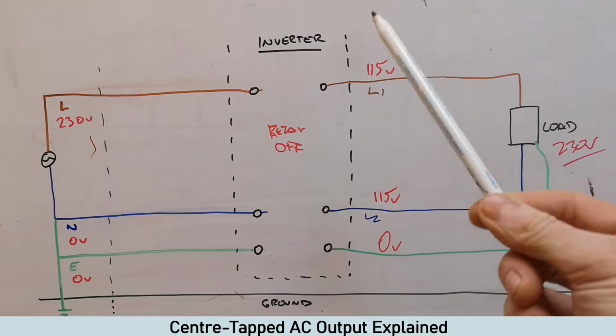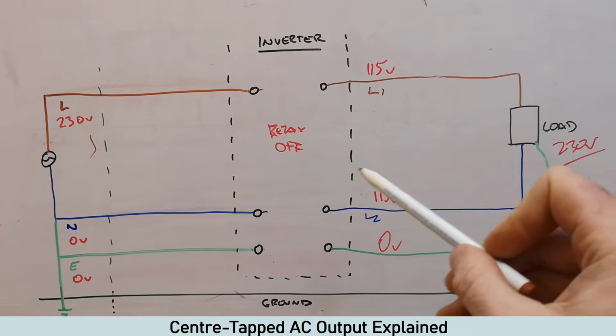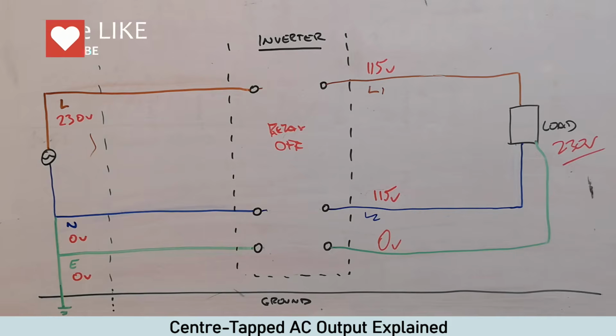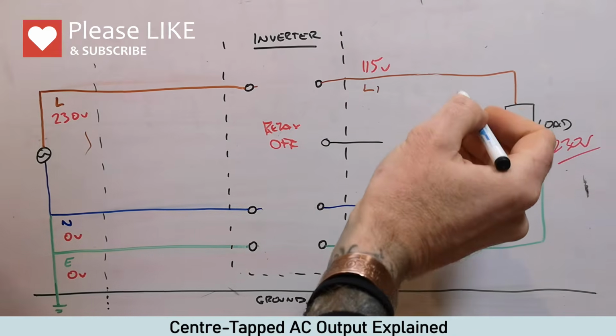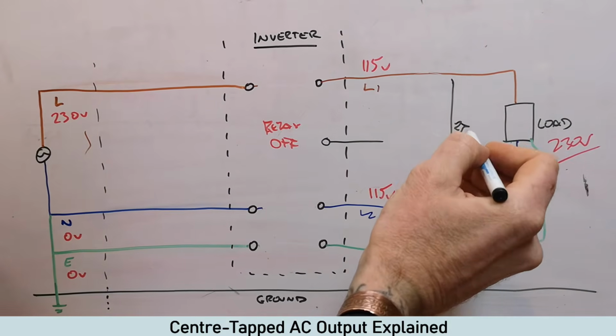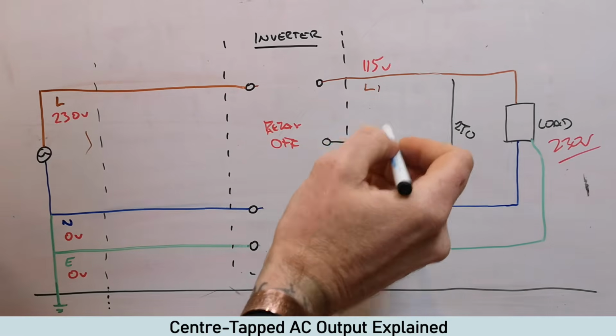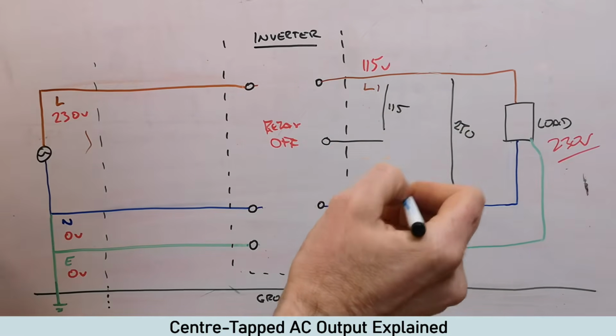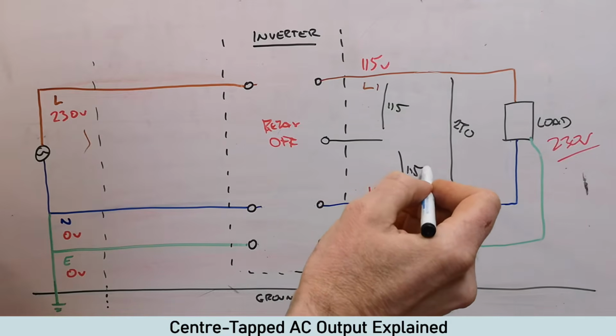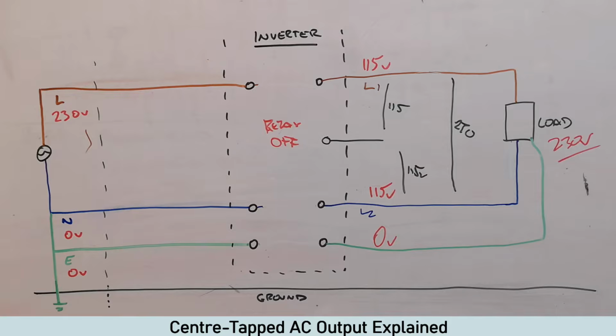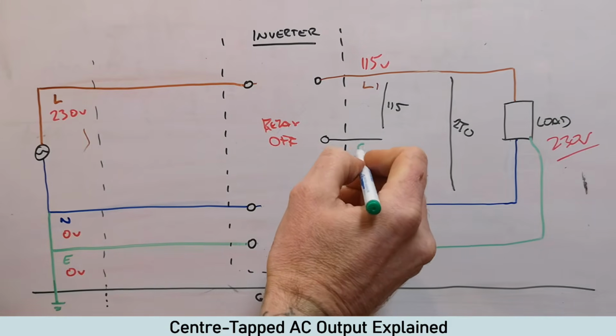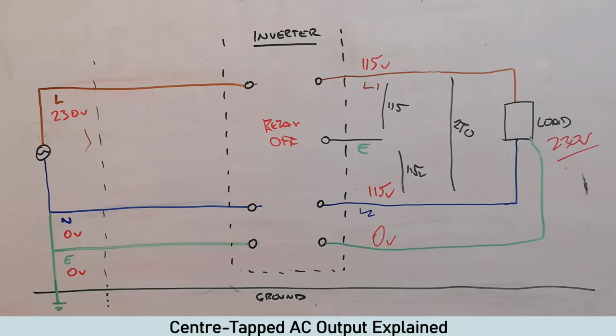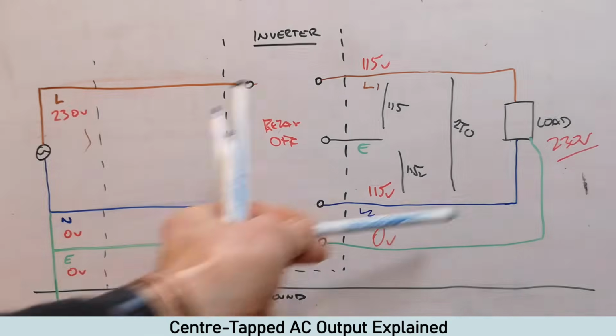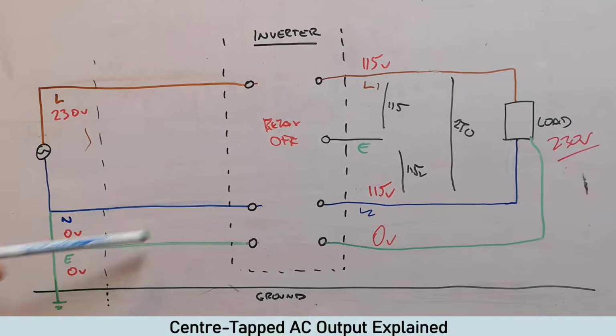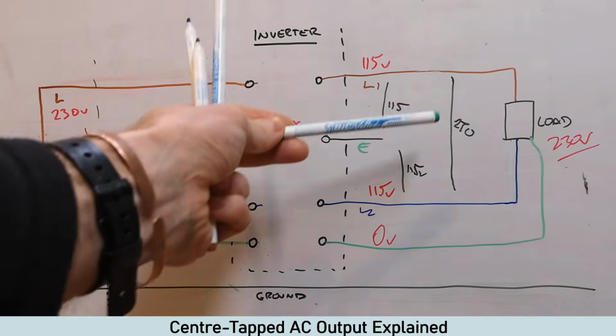Now, the reason for this is called a center tapped system. So what's actually happening is there's a link here coming out. So if you measure between these two, you're going to get 230. And because there's a central link here, if you go between those, you're going to get 115. And between that one and that one, you're going to get 115 volts. Now it's got what they call a center tapped earth, so that will be like an earth there, and that's why. They've moved the earth. I've got it there on the drawing, but if you imagine it in the center, rather than it being separate here, it's in the middle. So you're actually reading 115.